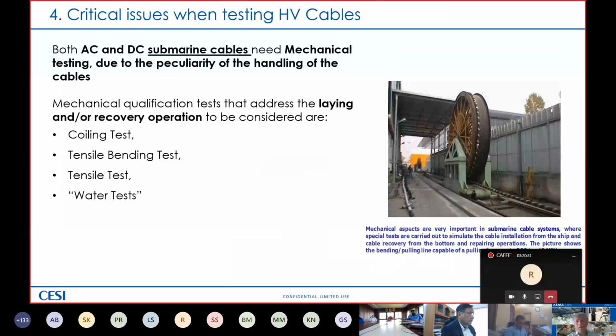Both AC and DC submarine cable, talking about submarine cable, I already mentioned, they need further mechanical testing due to the peculiarity of the handling of the cables. On the right side, there is a picture of a cable testing area that is located in Cesi, Milano, by the way, where special tests are carried out, tensile bending test, so-called, to simulate a cable installation from the ship and or the cable recovery from the bottom and repairing operation. This picture shows the bending and pulling line cable of pulling up to 200 tons.